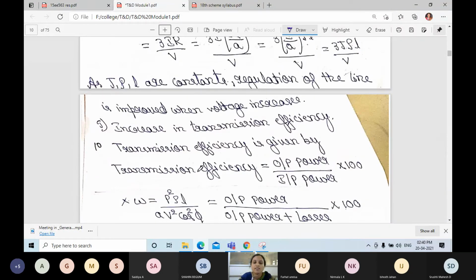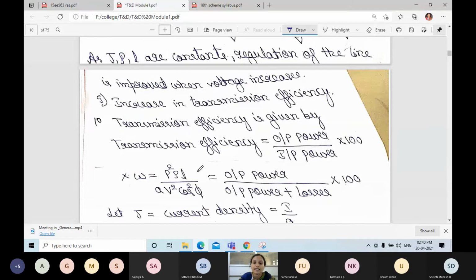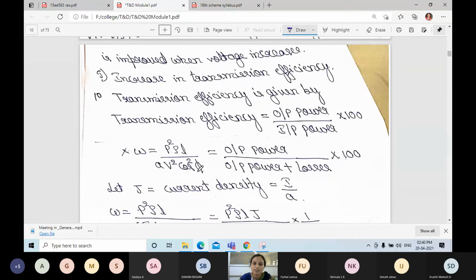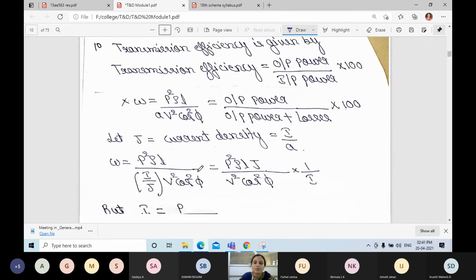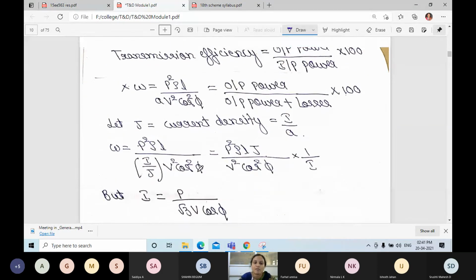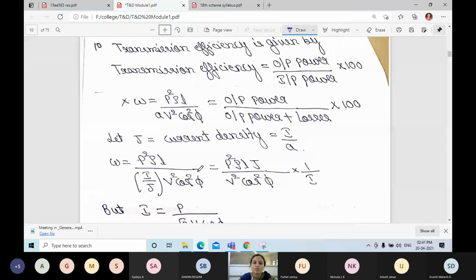Next advantage is increase in transmission efficiency. If losses are reduced, automatically you'll get higher efficiency. Here there is a formula: efficiency is output power divided by output power plus losses. If you substitute the formula, that is W equal to P square rho L divided by A V square cos square phi. That is the formula for losses.